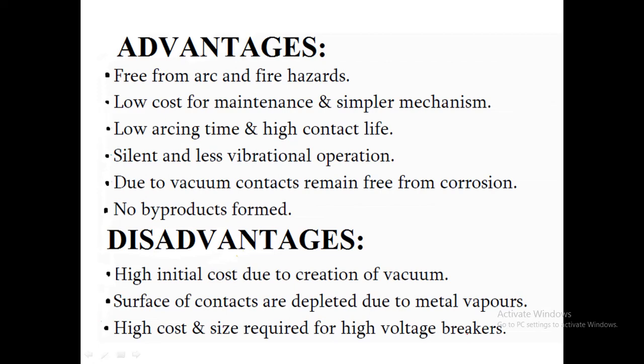Coming to the disadvantages, the main possibility of problems occurring in this type is erosion of material from the electrodes and evolution of gases from the electrode during the arcing. The gases are liberated from the electrode material due to metal evaporated by the anode and cathode, and surfaces exposed to the radiation from the arc, so that the gases are released. The gases are also released from the inactive portion of the electrode due to heat conduction.